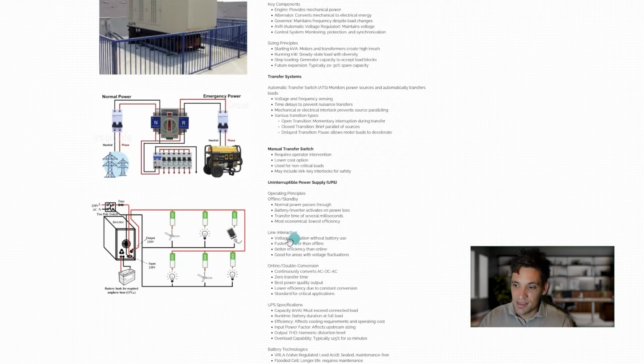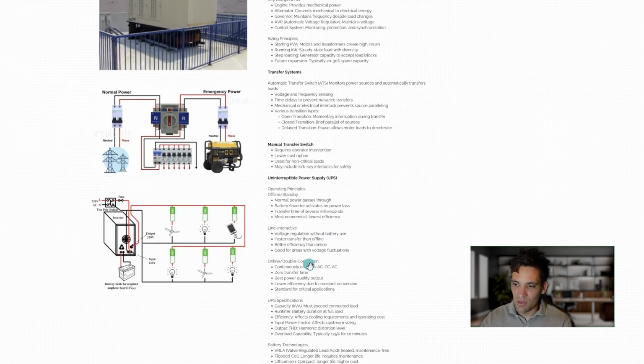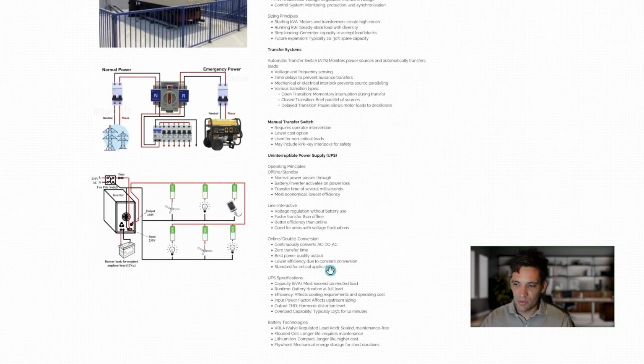For example, these UPS have different operating systems. You can have an offline, standby one where the normal power passes through and the batteries only activate when the power is lost. These are the most economical, but they have the lowest efficiency. You can have a line interactive UPS, which provides voltage regulation without battery use, but when the power drops out, they instantly switch on because the power is connected through the UPS. Or you can have online double conversion, which operates continuously. They're the most expensive, but they also have the fastest transfer time.